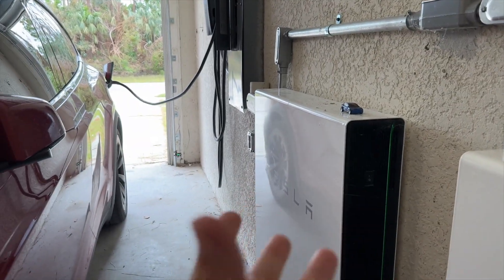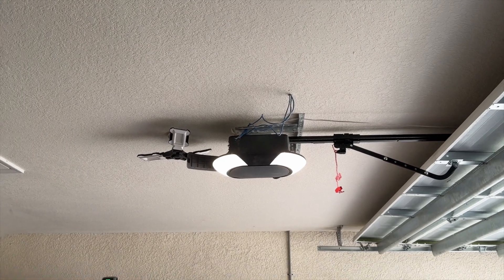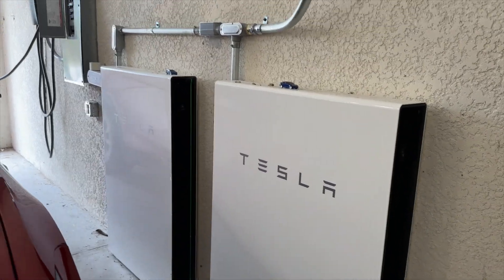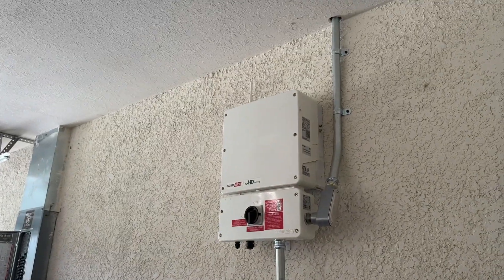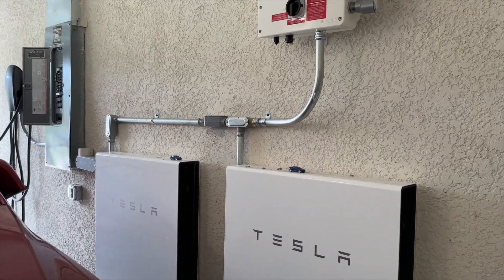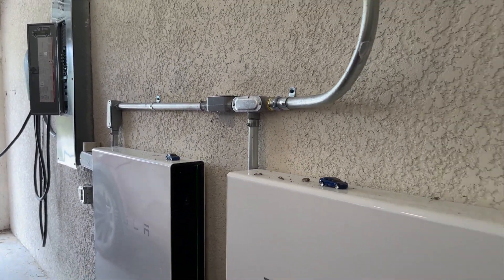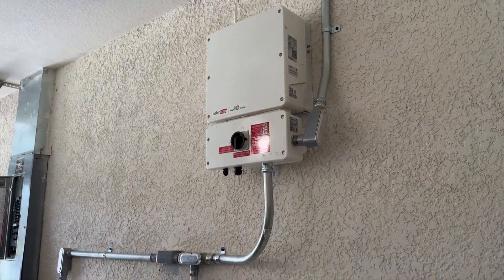When they were blinking, that means they were looking for signal, looking for power. I had all of this off — where it says GFI under pole right there — I flipped that on. It was enough to turn that power on, including the power above my garage. When I flipped that, the light automatically came on, the Powerwalls were on, and that gave enough power to the solar inverter to start. I connected to the Tesla Energy Gateway and waited for the solar to come back on — it came back on.